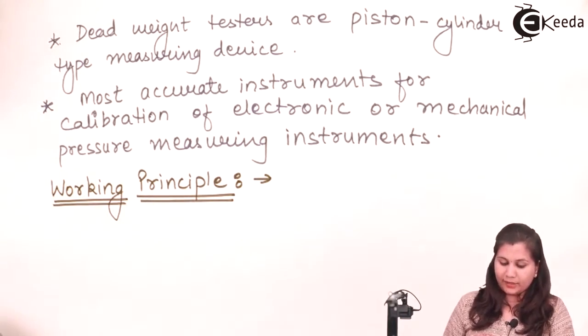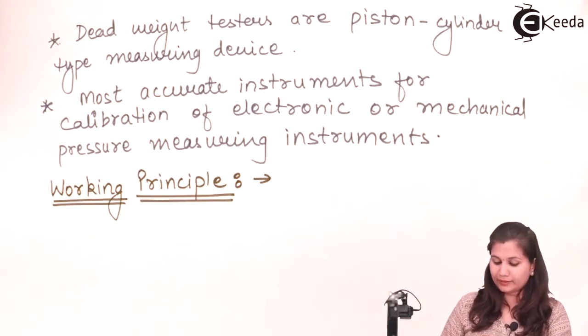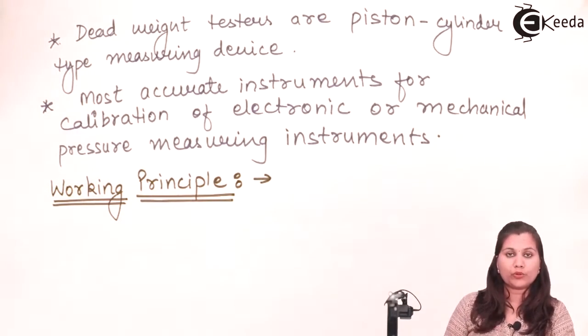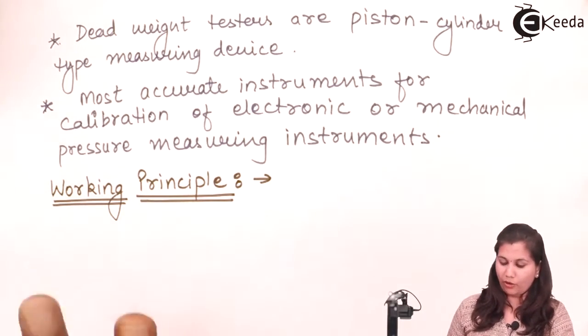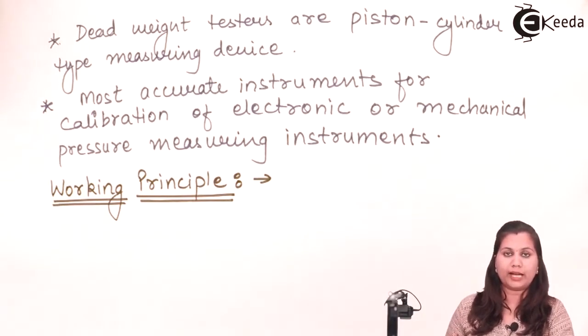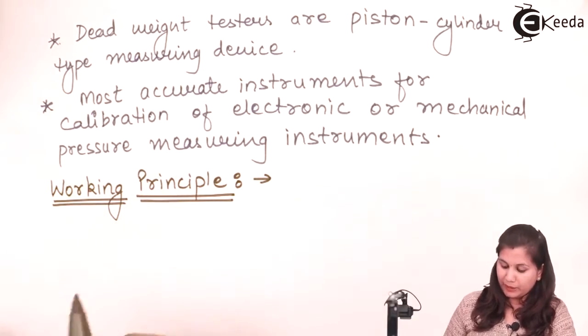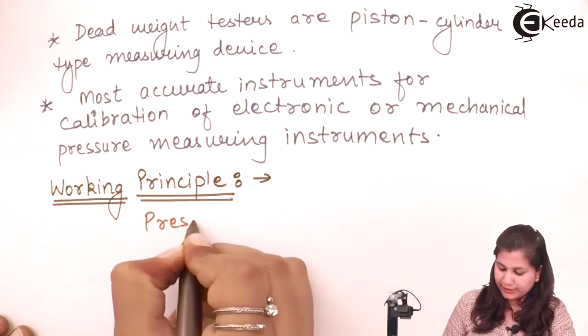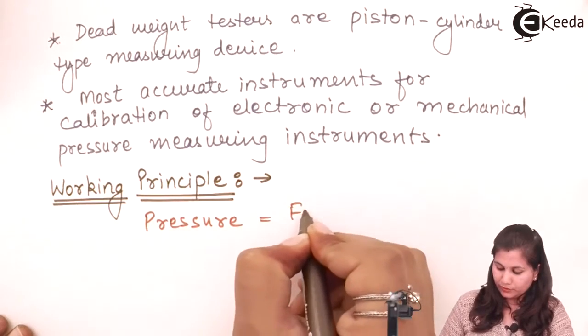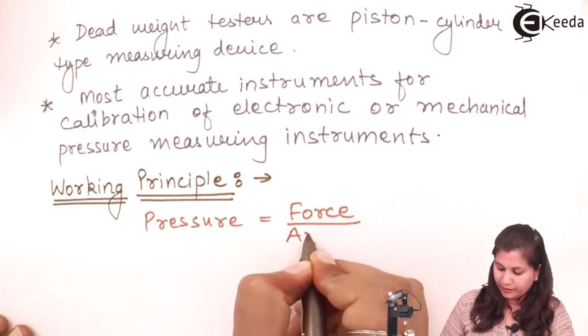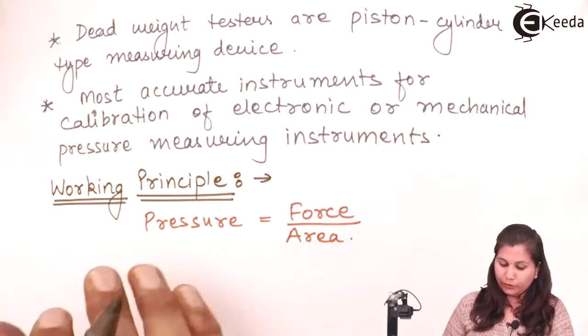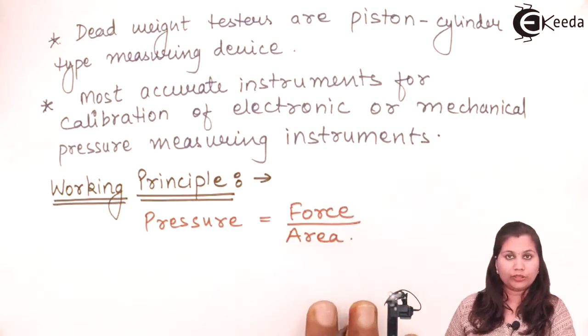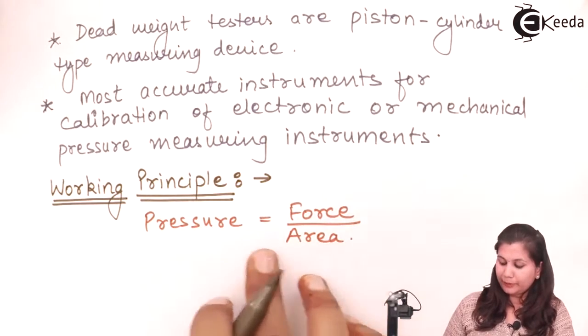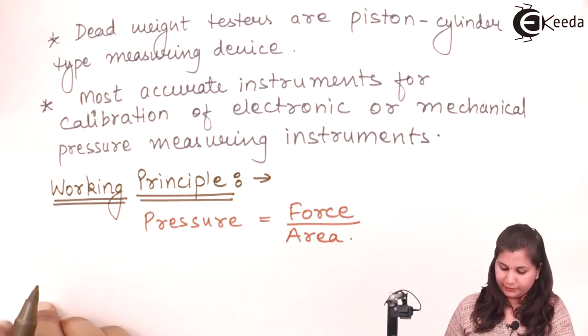The deadweight testers work in accordance with the principle that pressure is equal to force per unit area. Okay, so the pressure acts on a known area of the piston, and then it is going to generate a force over that piston. So the working principle is based on the formula that pressure is equal to force per unit area. A known pressure is applied on a known area of the piston, and due to that pressure, a force is generated.